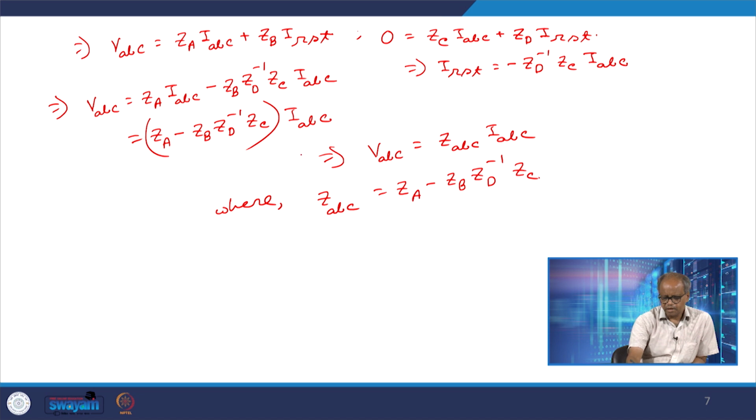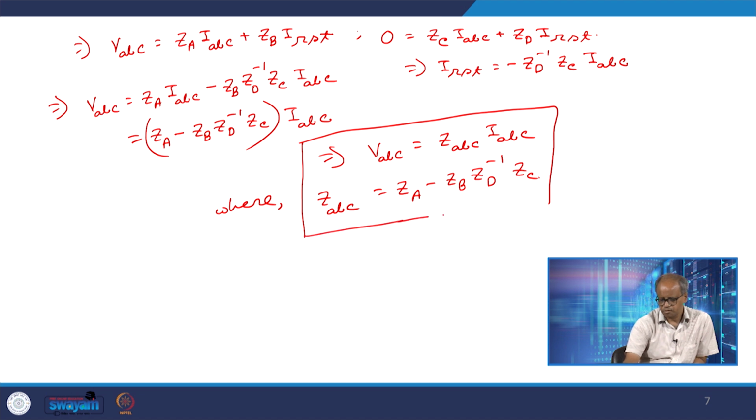Of course, this kind of calculation requires the help of a computer, but nowadays that is not a big problem. So that's how we can calculate the impedance matrix of a bundle conductor line where every phase has 2 bundle conductors. Of course, we can extend this principle in case there are more than 2 bundle conductors in every phase, but we are not going to discuss that, because in that case the cases would be endless.